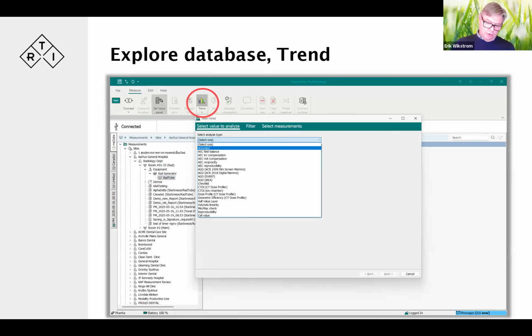Now for traceability and working with this, there's a trend function where we can explore the database, mine it for interesting data. For that we look at different analyses built in, and these are some of the analyses we have: accuracy, reproducibility, CTDI, half value layer, geometric efficiency for CT, linearity, reproducibility, minimum, maximum, all kinds.